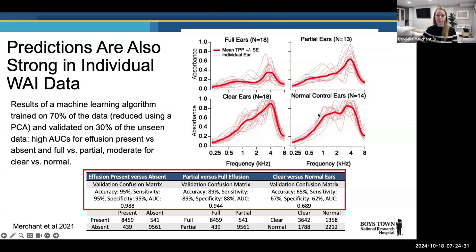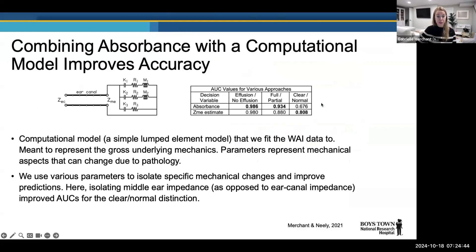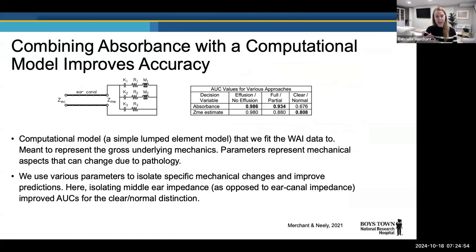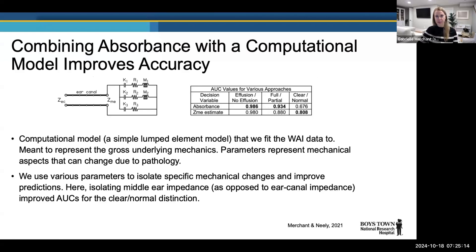We've also been working to improve sensitivity and specificity further by applying these wideband measurements to a computational model that removes the effect of the ear canal so we can really look at the characteristics of what's happening in the middle ear. That computational modeling approach does seem to improve sensitivity and specificity in some cases, and we're continuing to refine that model and identify which parameters are most diagnostically sensitive.